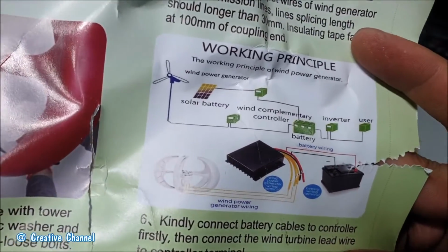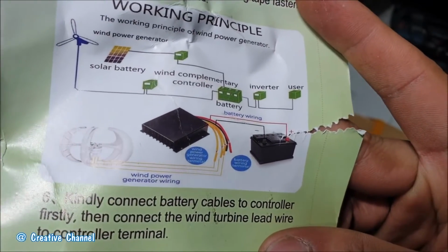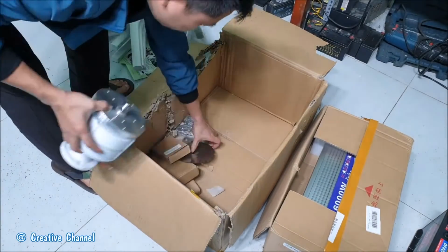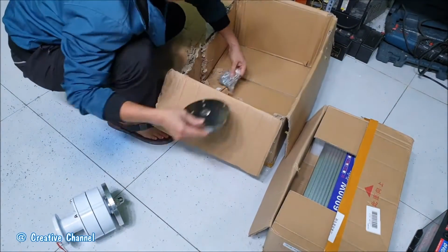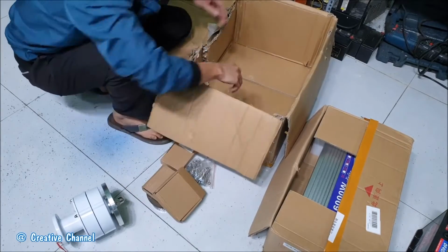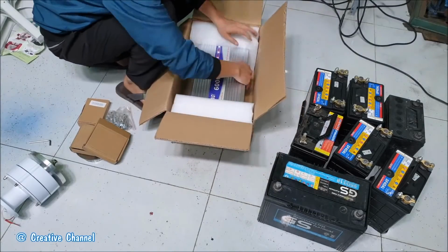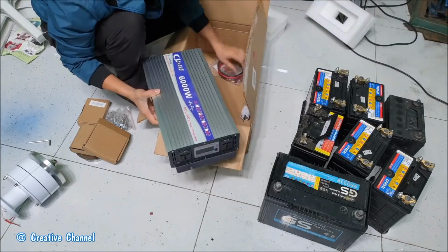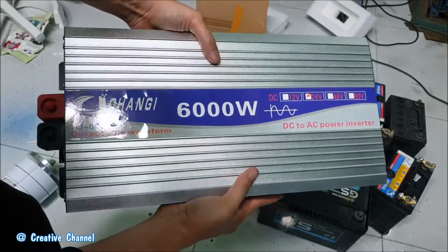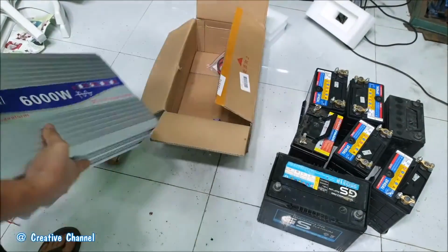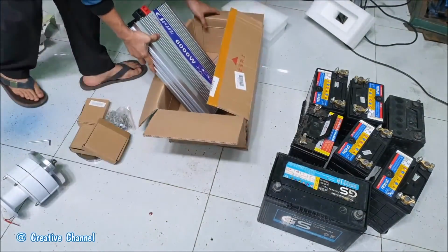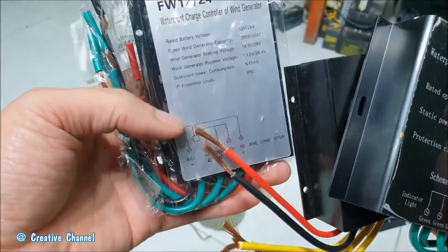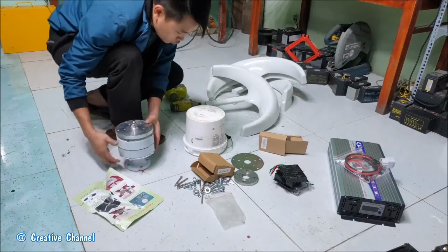Not to get too deep into the details, but wouldn't you need two separate inverters and two separate electrical systems that feed into your home or business? How does that work? No, we have a controller called a wind solar hybrid controller. The controller has two junctions. One is for a wind generator. It's an AC input with 3 wires, and another is a DC input with 2 wires.